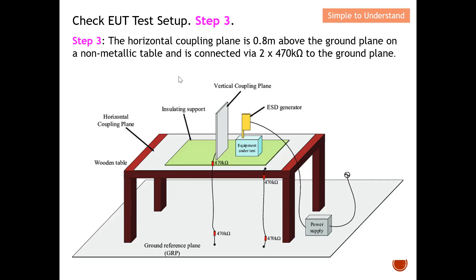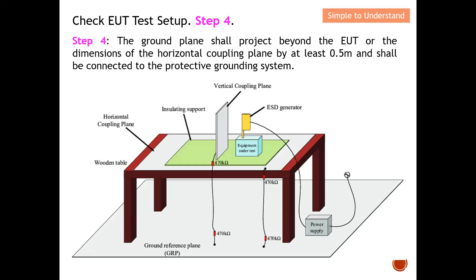Step number four: the ground plane should project beyond the EUT or the dimension of the horizontal coupling plane by at least 0.5 meters, and should be connected to the protective ground system. The ground plane must extend at least 0.5 meters outside the horizontal coupling plane on all sides.